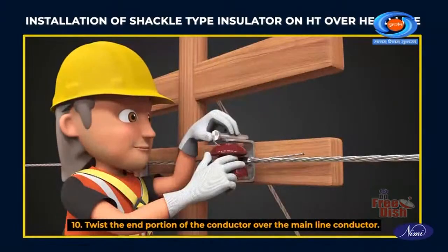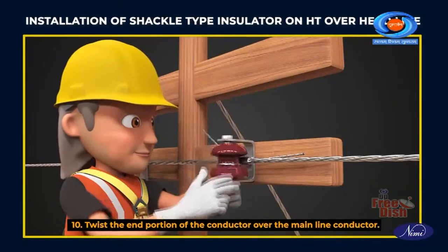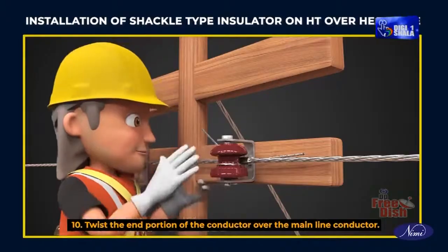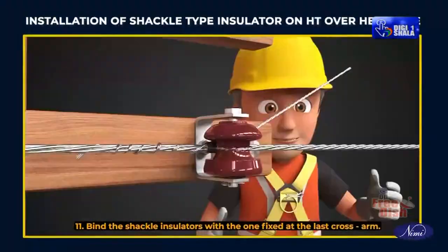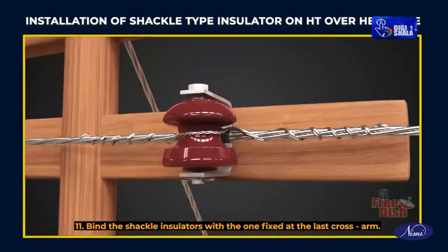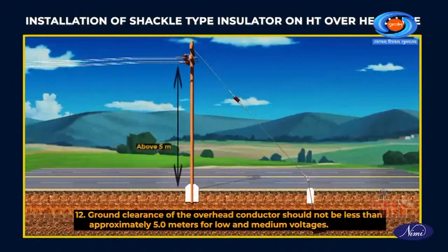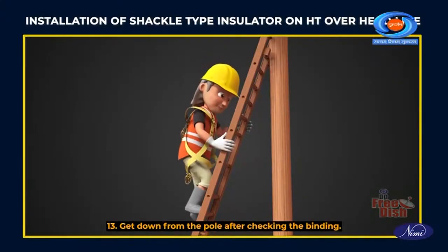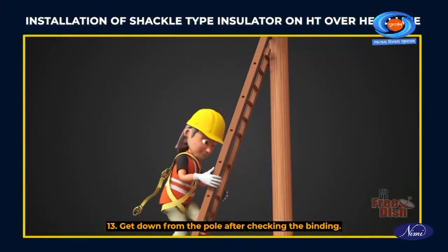position. Twist the end portion of the conductor over the main line conductor. Bind the shackle insulators with the one fixed at the last cross arm. Note: ground clearance of the overhead conductor should not be less than approximately 5 meters for low and medium voltages. Get down from the pole after checking the binding.